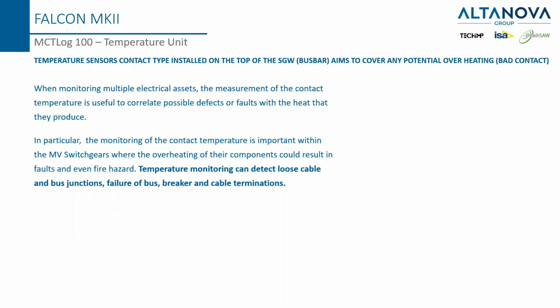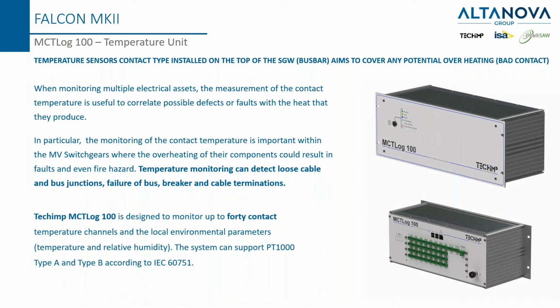Regarding the temperature monitoring features of the Falcon Mark II, there is another 19 inch rack to host in the same enclosure, to which up to 40 contact temperature sensor channels can be connected. This actually has a consistency with the Falcon unit that can monitor up to 40 partial discharge channels. So they are designed to be put together in the same cabinet.